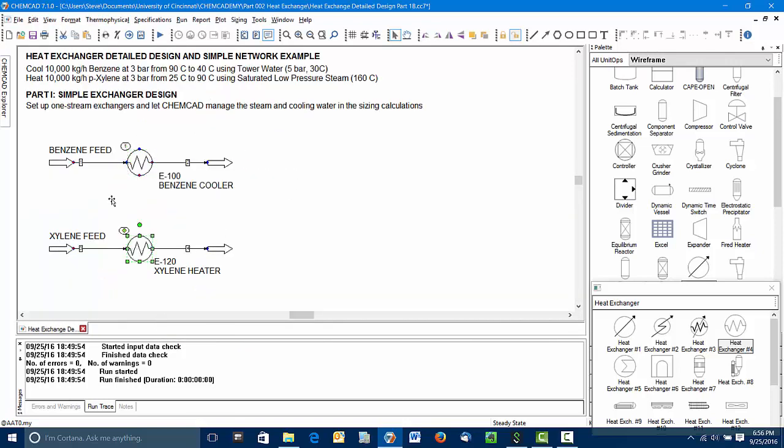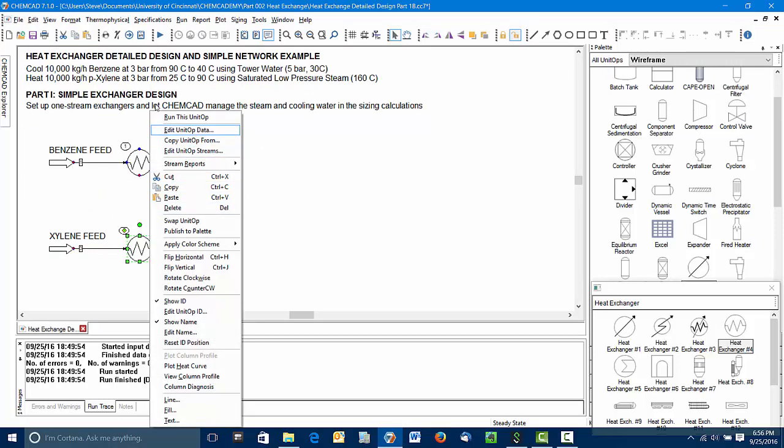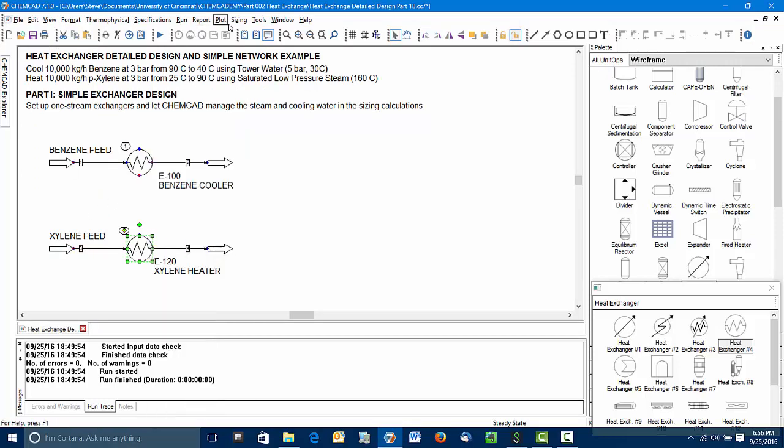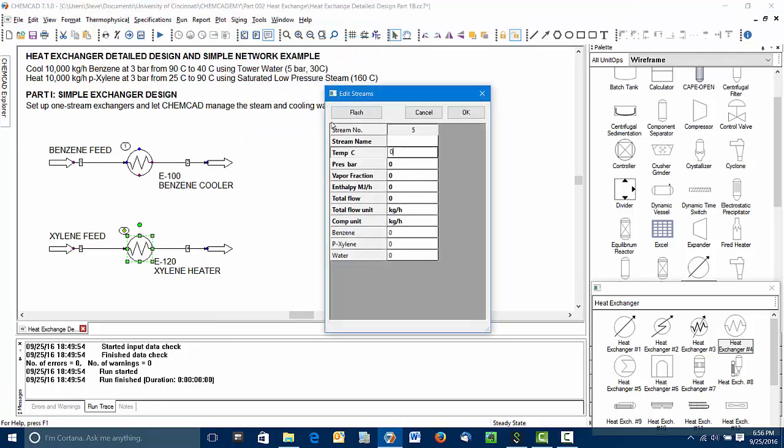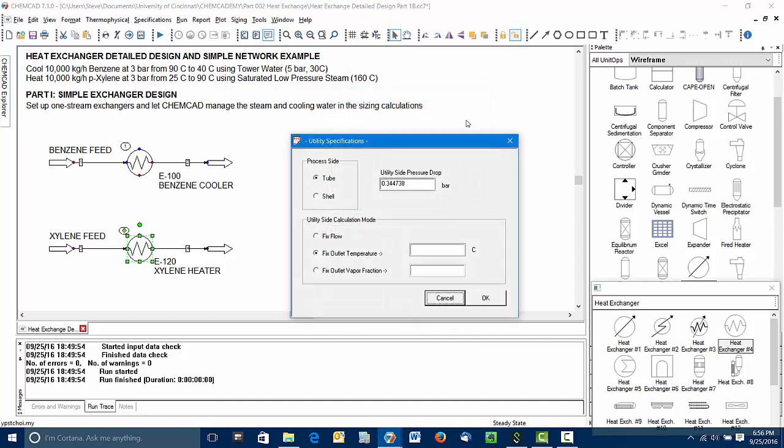Let's do the same thing for the xylene heater. We're going to go to sizing, heat exchangers, shell and tube. In this case, our utility is saturated low pressure steam. So we're going to give the steam pressure and we're going to give the vapor fraction because it's saturated. And ChemCAD will calculate now the temperature. We don't know the flow rate, so we'll just give it a number. ChemCAD goes to the same set of questions here. We again identify that the xylene is on the tube side, the steam is on the shell side. Now we can fix either an outlet temperature or an outlet vapor fraction. In this case, let's set the vapor fraction. If we leave this zero, ChemCAD doesn't always handle zeros properly. So let's put instead of zero a very small number. So basically we condensed all but a very, very tiny fraction of our incoming steam.